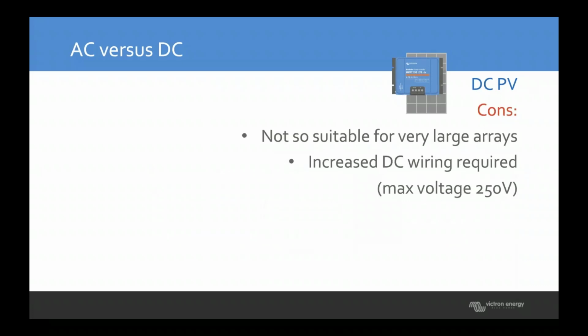The cons are they're not very suitable for very large arrays. We do sell quite a large DC MPPT, but it's still only limited to about 5 kilowatts, 100 amps at 48 volts. Fronius do much, much larger AC PV inverters than 5 kilowatts. So if you're doing very, very large systems, then AC PV is definitely worth considering. DC wiring is also required. The lower voltage on the panels means you need higher currents to get the same power: thicker wiring, shorter runs, and lower maximum PV panel voltages.